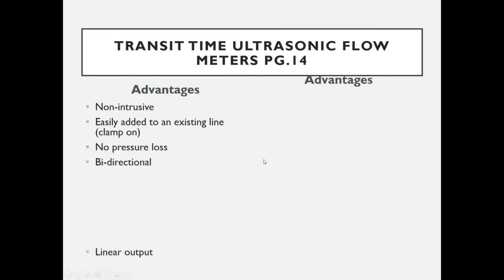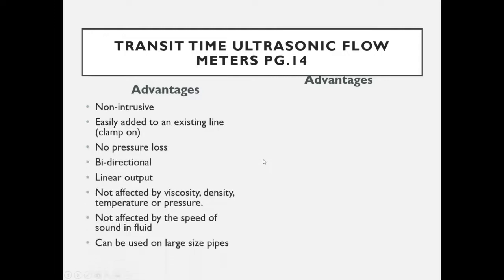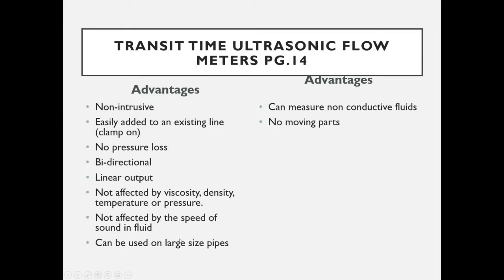Transit time advantages: non-intrusive, can be clamped on, no pressure loss, bi-directional, linear, not affected by viscosity, density, temperature, pressure, or speed of sound. Additionally, transit time can be used on large pipe sizes, is good for measuring non-conductive fluids, and has no moving parts — making it suitable for a quite a few applications including both liquids and gases depending on the technology.